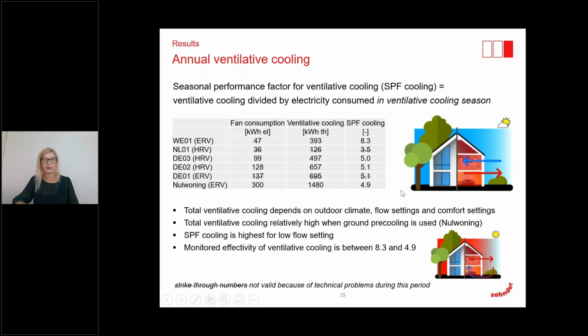But here again, we need to think about the fact that this data has been collected in the Central Europe solutions, and we need to consider the outer climate, the temperature and humidity, the flow settings of the system, and also the comfort settings of the system. For example, where we have set the temperature. Is it rather cool or warmer? This is also something the unit calculates to open the bypass in a modulated way, or how to control the airflows in the unit.